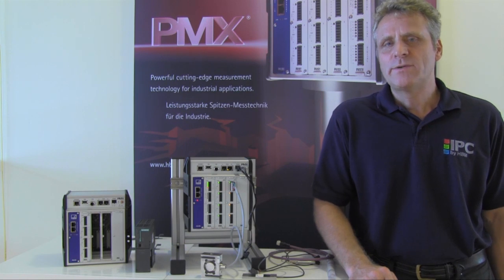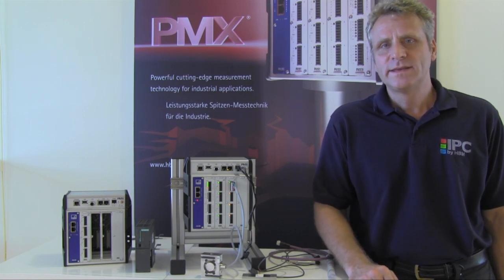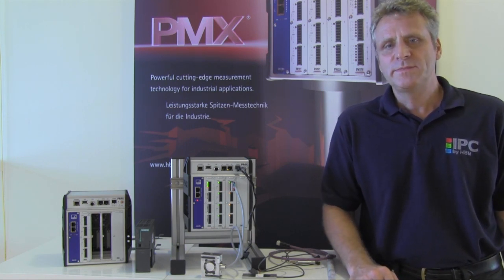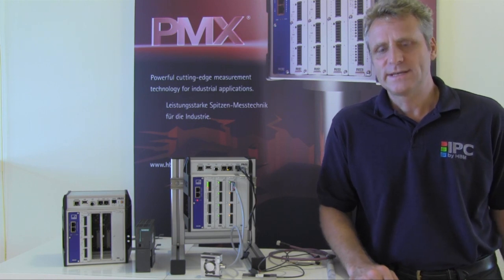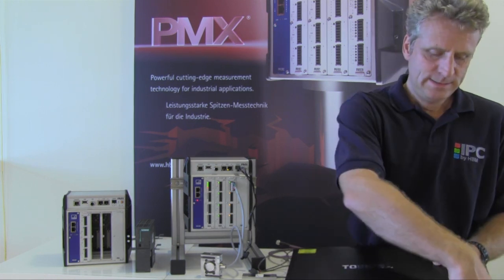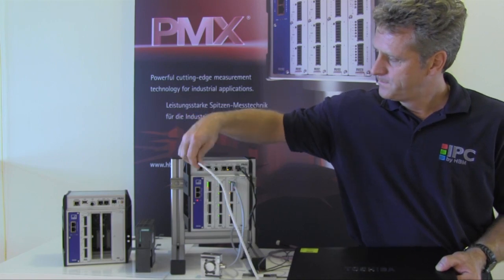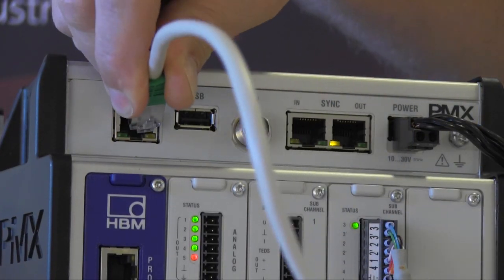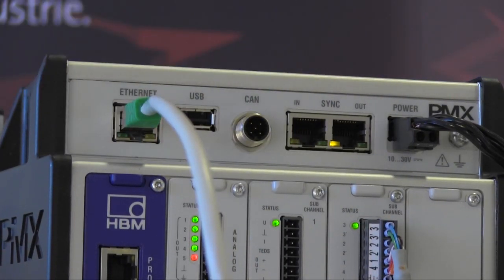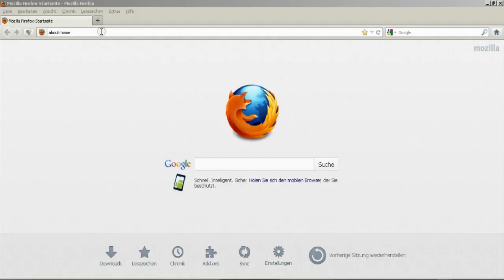Now let's connect the PC to the PMX for further operation via web server or the HBM Catman software. As mentioned earlier, the connection is made via Ethernet. Nothing else is needed. To create a connection to PMX devices, either the device name or the set IP address of the devices must be entered in the browser line.